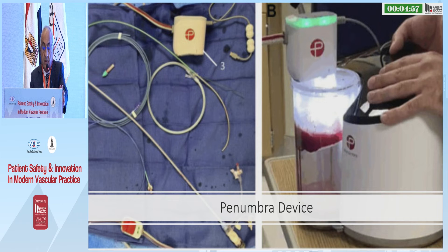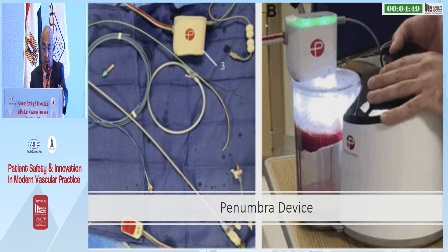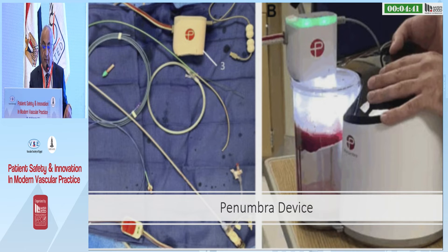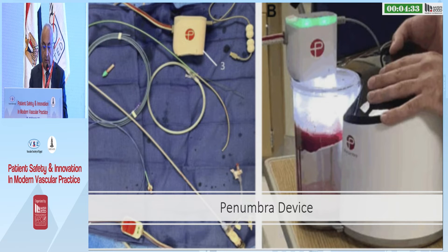This is the computer-assisted mechanical aspiration device — the Penumbra device. It is a pump that aspirates the clot. When the catheter is inside the clot it aspirates; when the catheter is in a patent vein, it stops aspirating automatically, thereby reducing blood loss. It also has a separator that, when withdrawn inside the catheter, helps remove the thrombus.